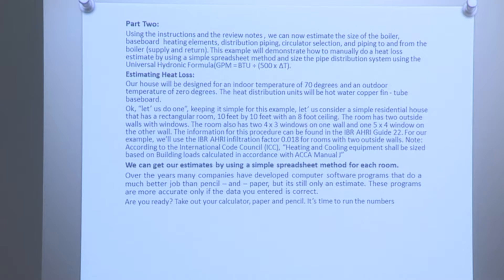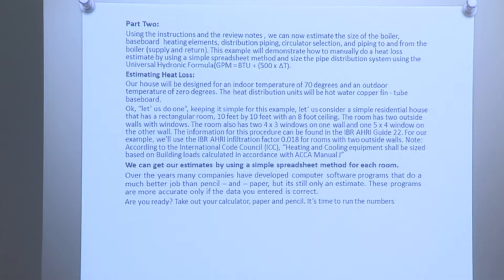Part 2: using the instructions and review notes, we can now estimate the size of the boiler, baseboard heating elements, distribution piping, circulator selection, and piping to and from the boiler supply return. This example demonstrates how to do a heat loss estimate using a simple spreadsheet method and size the pipe distribution system using the Universal Hydronic Formula: GPM equals BTUs divided by 500 times delta T. Our house will be designed for an indoor temperature of 70 degrees and outdoor temperature of 0 degrees. The heat distribution units will be hot water copper fin tube baseboard. Let's consider a simple residential room that is 10 feet by 10 feet by 8 feet with two outside walls with windows — two 4 by 3 windows on one wall and one 5 by 4 window on the other wall. This information can be found in the IBR AHRI Guide 22.